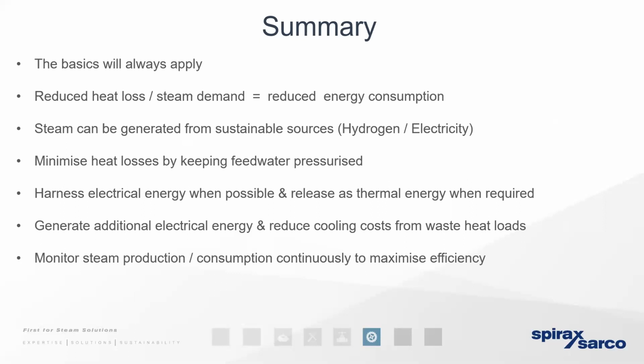We also know that we may be in a position to replace a traditional fossil fuel fired steam boiler altogether and replace it with one of those electrical steam generators that we've spoken about. But we also have the ability to utilize that thermal store to charge pressurized hot water from renewables and to distribute that to the process whenever there's a demand. We can also use that pressurized deaerator that we've spoken about to help move towards zero losses.